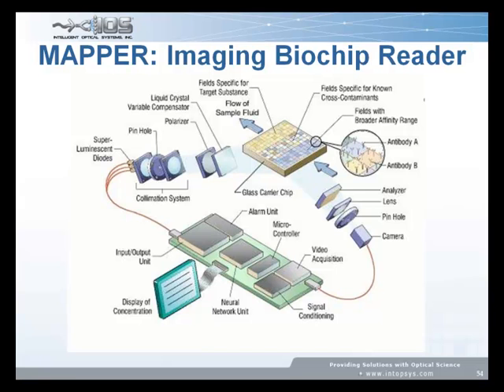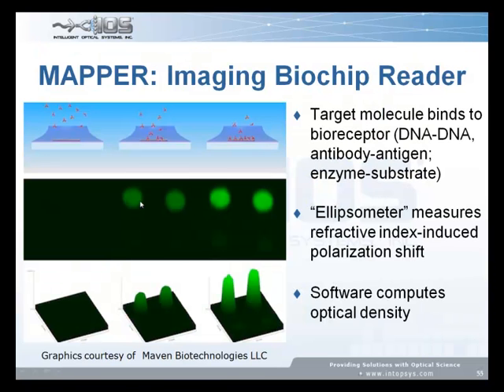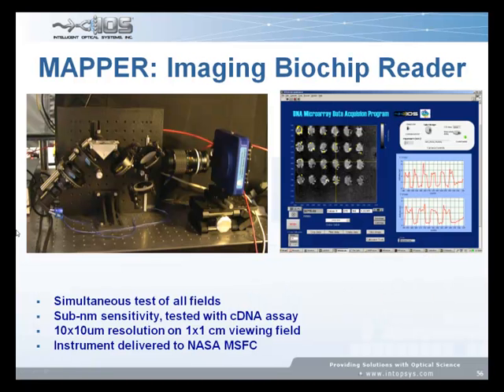So the way it works is you lay down your recognition elements, and we've done both nucleic acid as well as protein-based recognition elements on the surface. Lay down your recognition elements and set your optics up so that you have minimum light being reflected from the surface. You work basically right near the critical angle of total internal reflection. You don't have to be at the critical angle, but that gives you the highest sensitivity. And unlike surface plasmon resonance, the angle that you work at isn't all that critical, because what you're looking at is the rotation of the plane of polarization, not nulling, like you are with SPR. So as you get more and more binding, you get a larger and larger shift in the polarization of the reflected light.